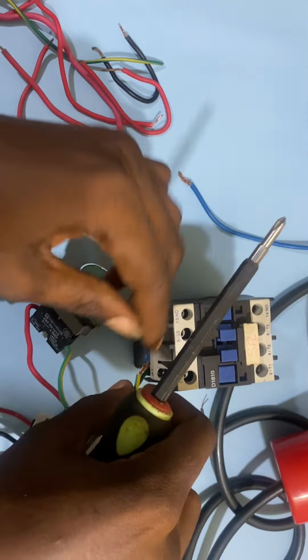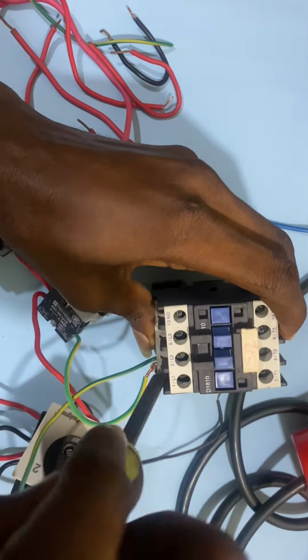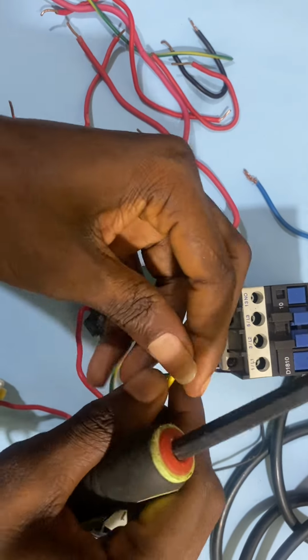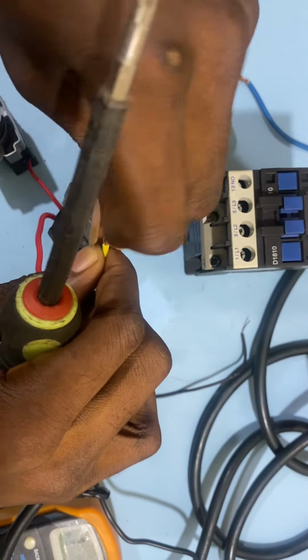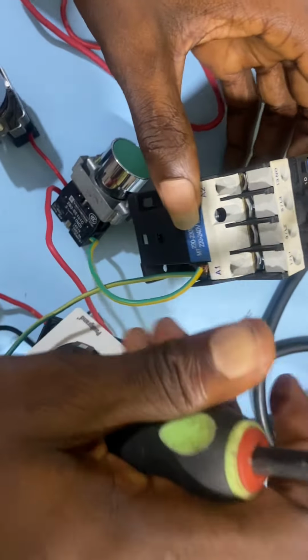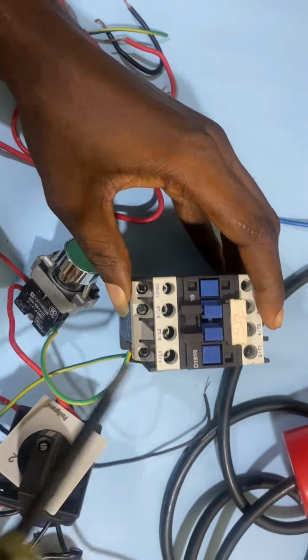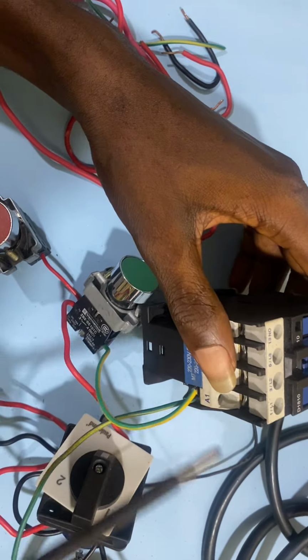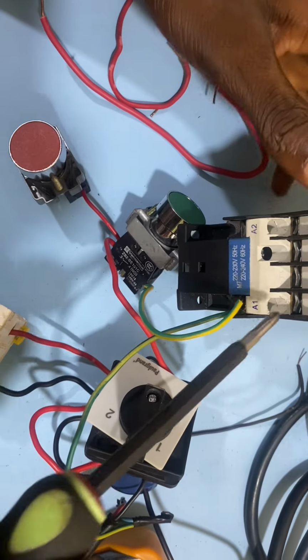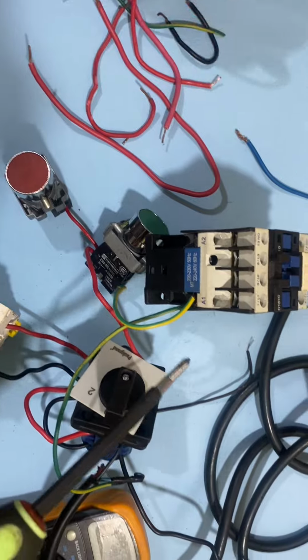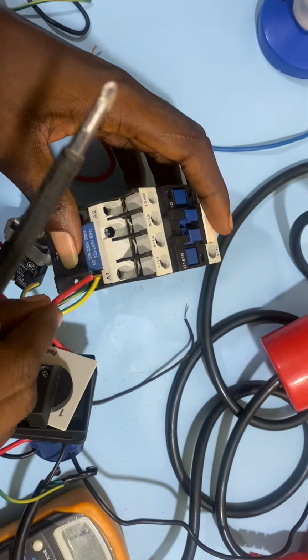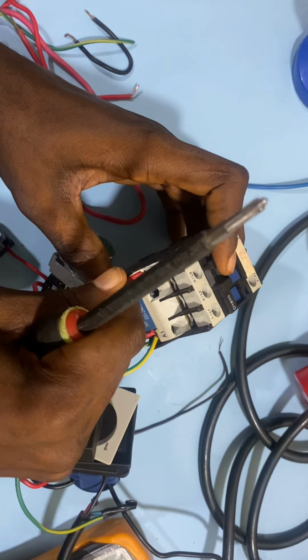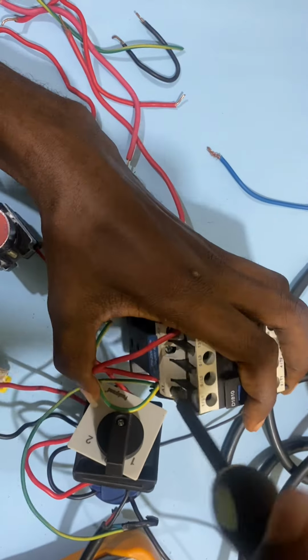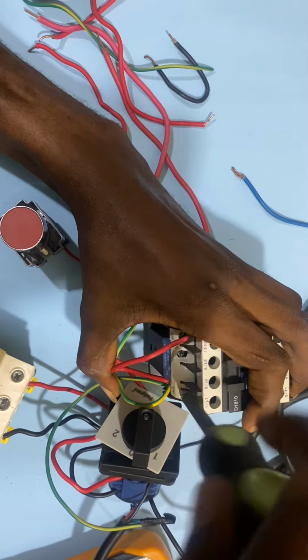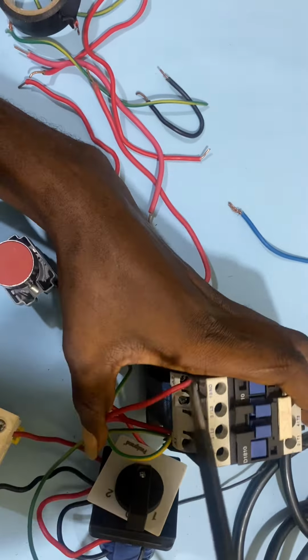Therefore it means that the live cable that is coming from the flow switch and the one that is coming from the start and stop button are connected together, and they loop to the normally open contact of the contactor. So connecting it here together at this point. Good. So it's at this position now. That is a live wire from the selector switch, and from the flow switch, from the start button. So I'm going to loop from this A1 now to the normally open contact of the contactor to create a holding contact. So let's do that together. I'm going to loop from here to this point. That is to create a holding contact for the start and stop button. That is for the start of the contactor.